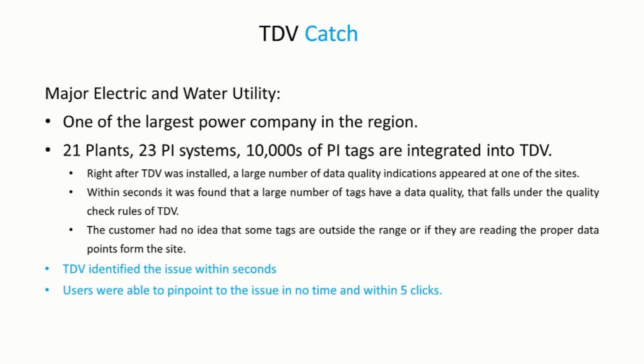Right after TDV was installed, a large number of data quality indications appeared at one of the sites. The customer was surprised and thought something was wrong, but within seconds we found that a large number of tags had data quality that falls under the quality check rules of TDV. The customer had no idea that some of the tags were actually reading outside the range, or whether they were reading proper data points from the site.